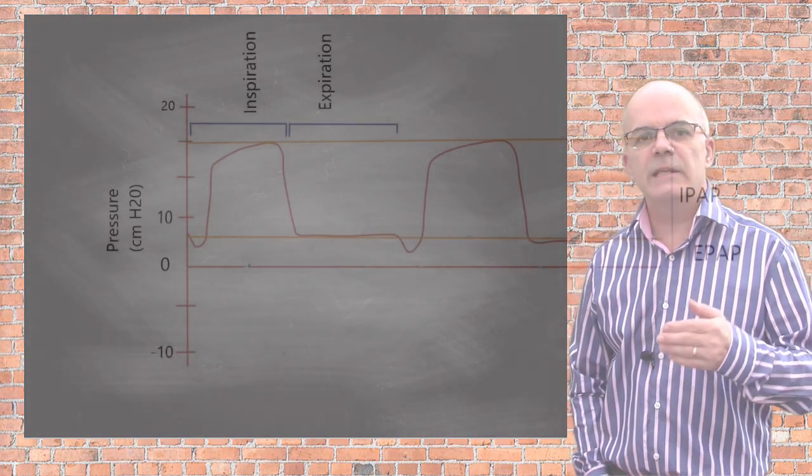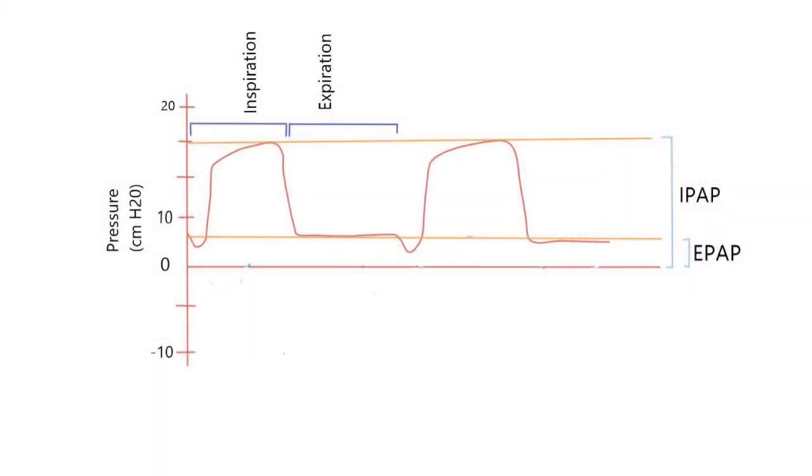In BiPAP, the patient triggers an inspiration by a sudden downward deflection in the airway pressure. When the machine senses this, it delivers positive pressure equal to the IPAP. Airflow increases into the alveoli, and as it reaches the IPAP set, then flow will drop.